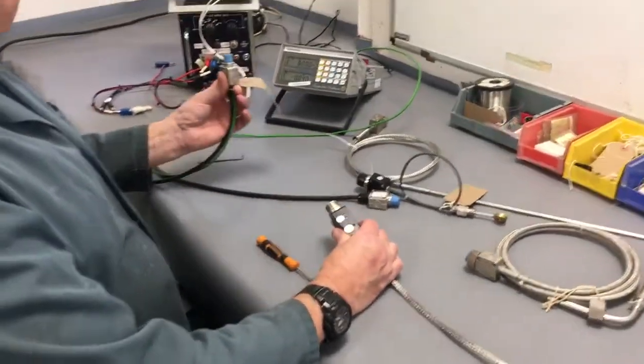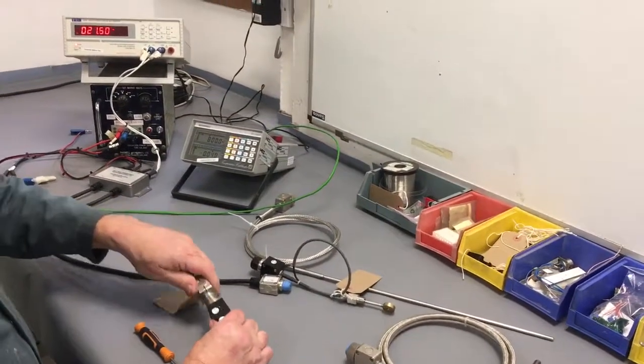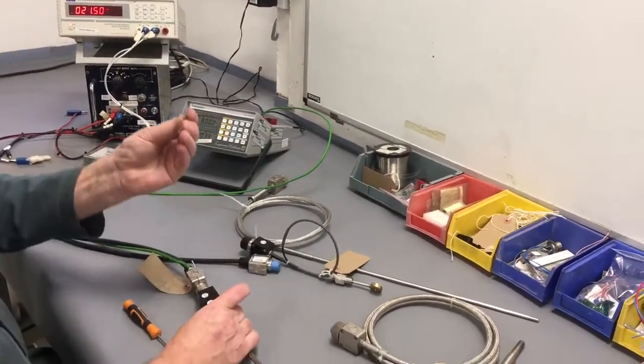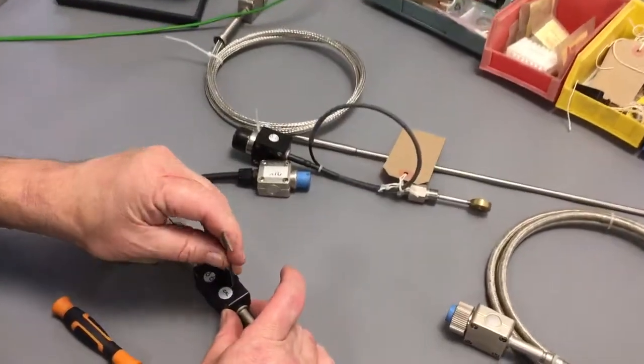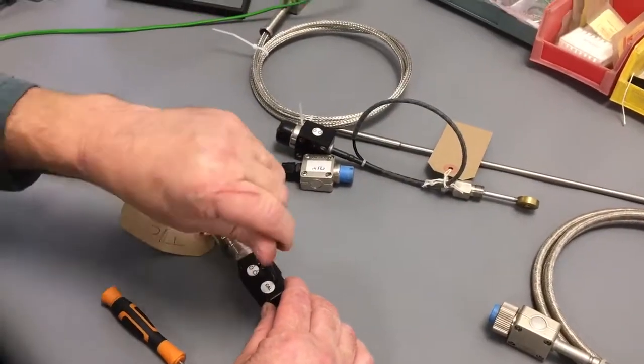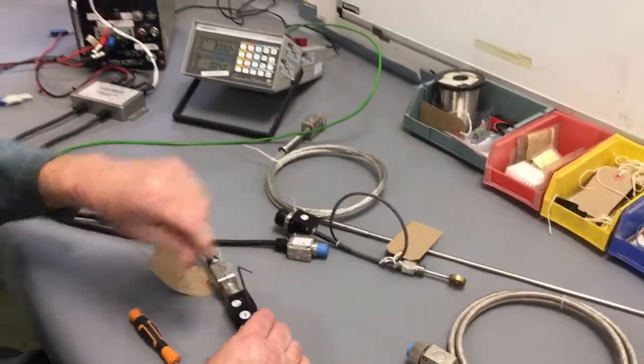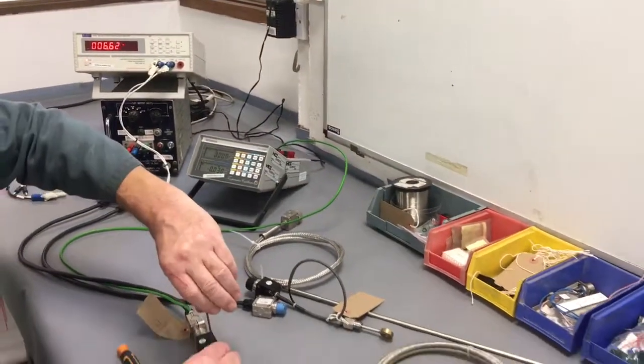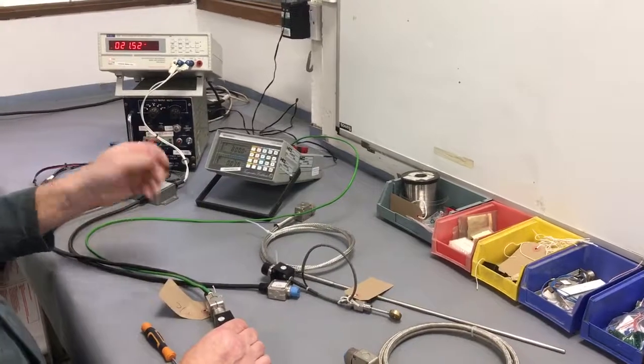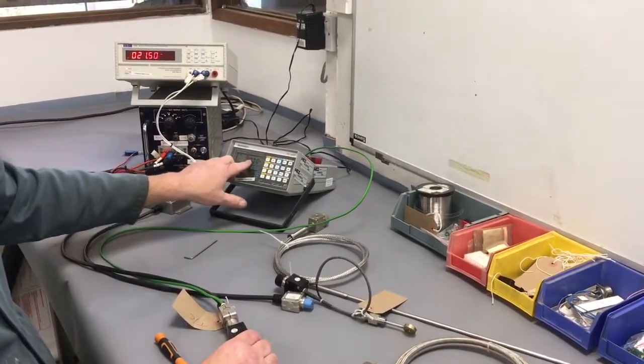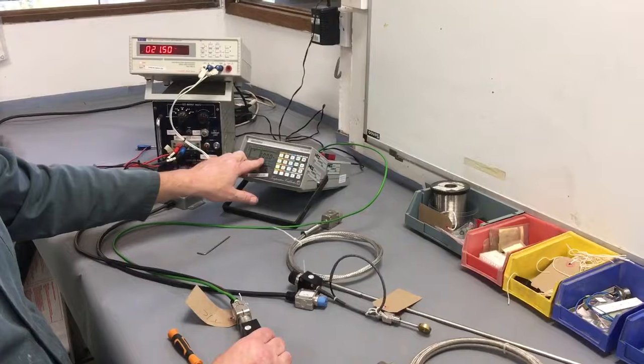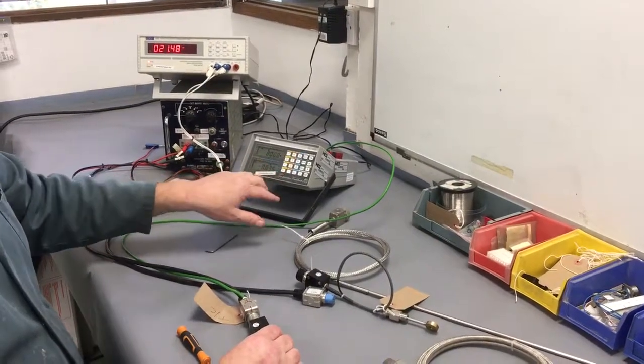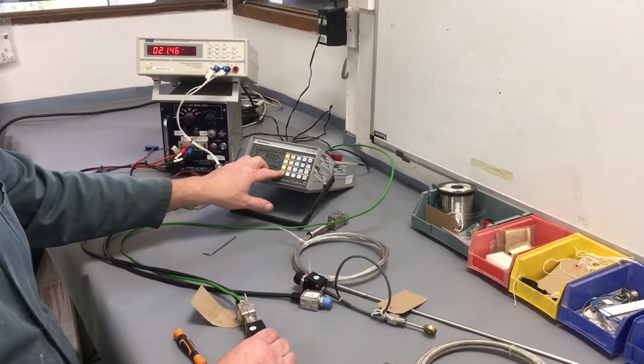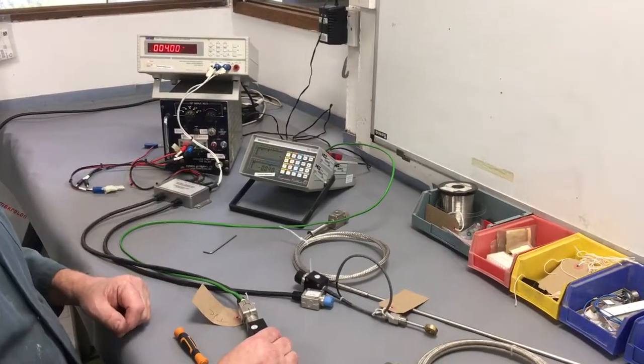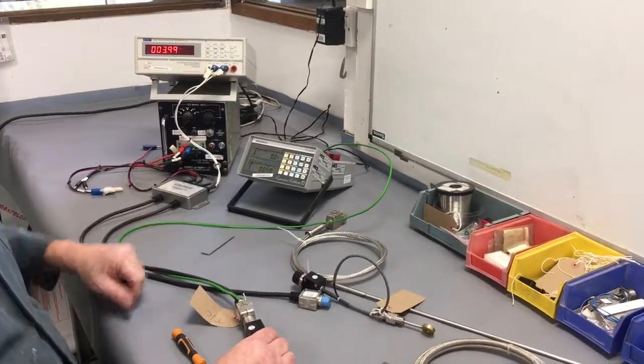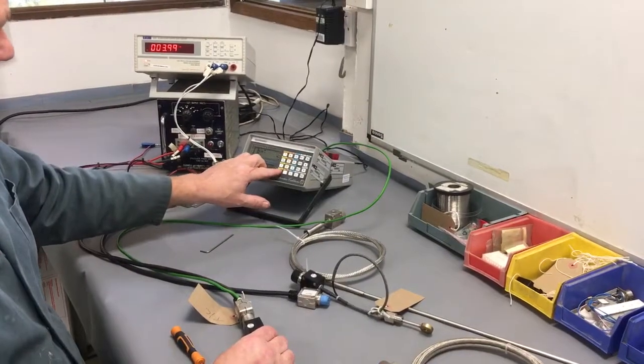So to calibrate this sensor, the sensor is fitted with a switch, and you need a 2.5 Allen key. The 2.5 Allen key will close the circuit, at which point you cannot calibrate. At which point you open the circuit, and now you can calibrate. So we now are injecting 800 degrees centigrade millivolts. So if we try initially to do 0 centigrade, so we have 4 milliamps at 0. We will then correct the 800. This is how easy it is to do.